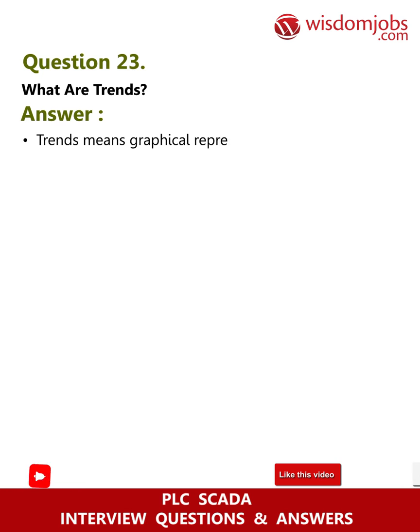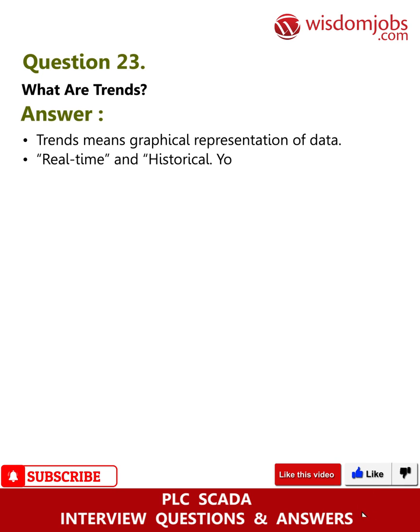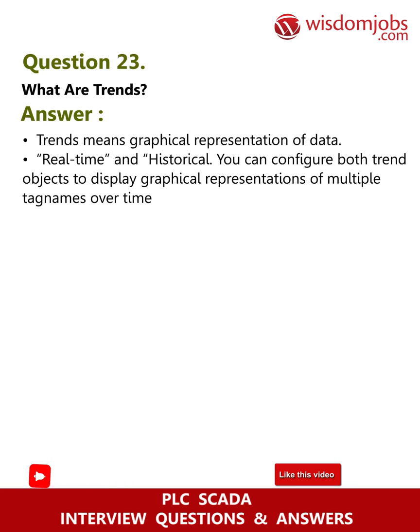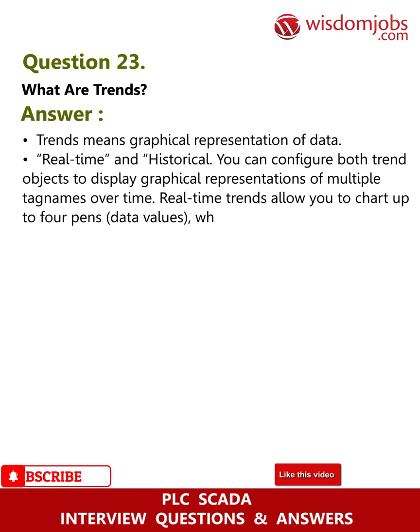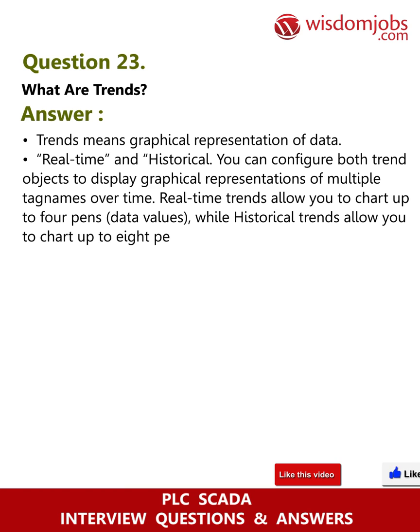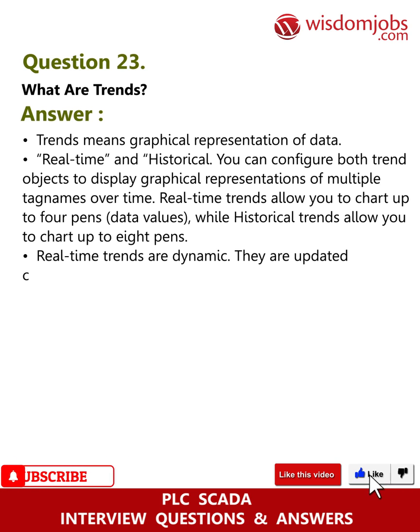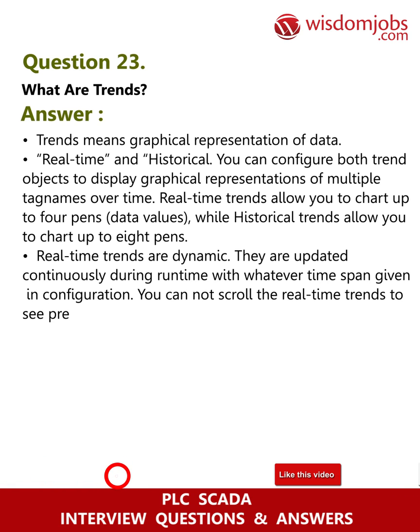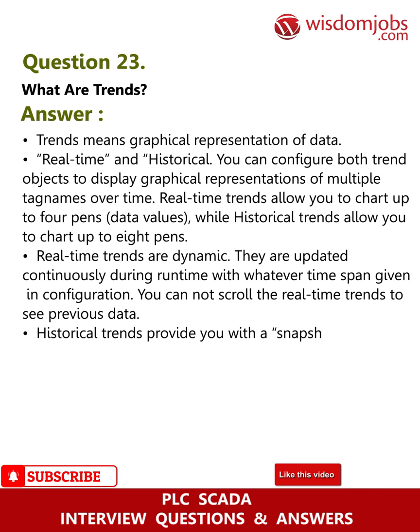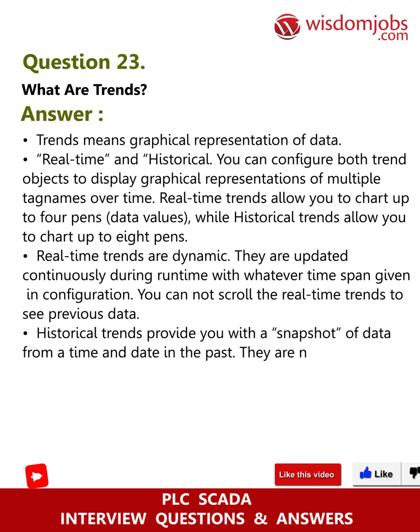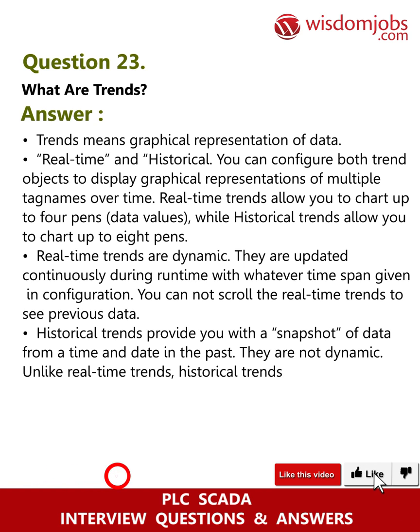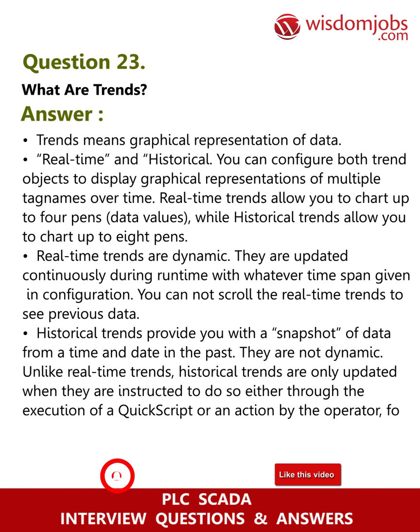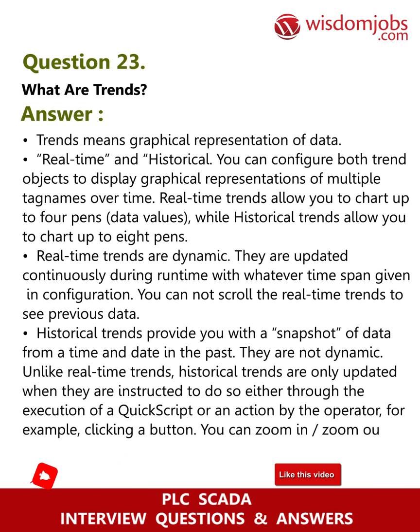Question 23: What are trends? Answer: Trends means graphical representation of data — real-time and historical. You can configure both trend objects to display graphical representations of multiple tag names over time. Real-time trends allow you to chart up to four pens (data values), while historical trends allow you to chart up to eight pens. Real-time trends are dynamic — they are updated continuously during runtime with whatever time span is given in configuration; you cannot scroll real-time trends to see previous data. Historical trends provide a snapshot of data from a time and date in the past; they are only updated when instructed, either through a quick script or an operator action such as clicking a button. You can zoom in and zoom out on trends and also access previous data.